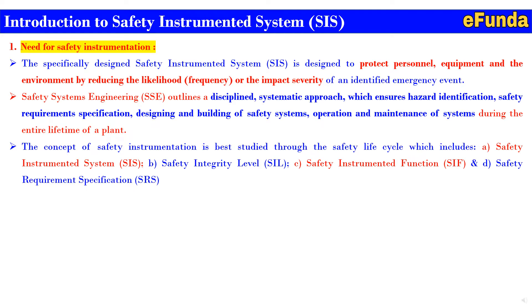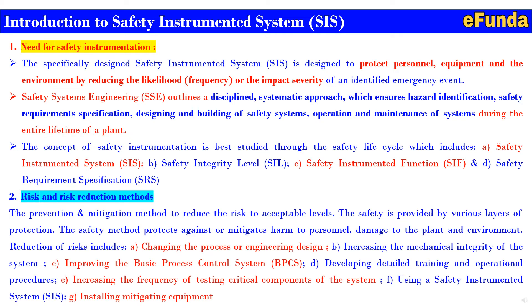The concept of the safety instrumented system is studied through the safety life cycle, which includes the SIS, safety integrity level (SIL), safety instrumented function (SIF), safety requirement specification (SRS), risk and risk reduction methods, and prevention and mitigation methods to reduce risk to an acceptable level. Risk reduction includes changing the process or design engineering, increasing the mechanical integrity of the system, improving the basic process control system (BPCS), developing detailed training and operational procedures, increasing the frequency of testing of critical components, and using a safety instrumented system and installing mitigating equipment.